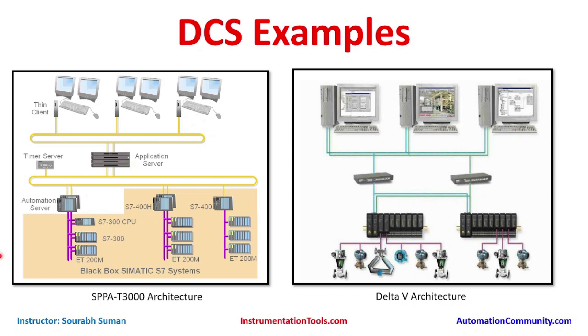The automation server hosts the application. It could be an AS3000 or CS3000 acting as the automation server; in some cases an S7 is also used in this role. All these controllers are connected in a network called the automation highway. A time server also resides on the same network so that all connected devices can be synchronized.